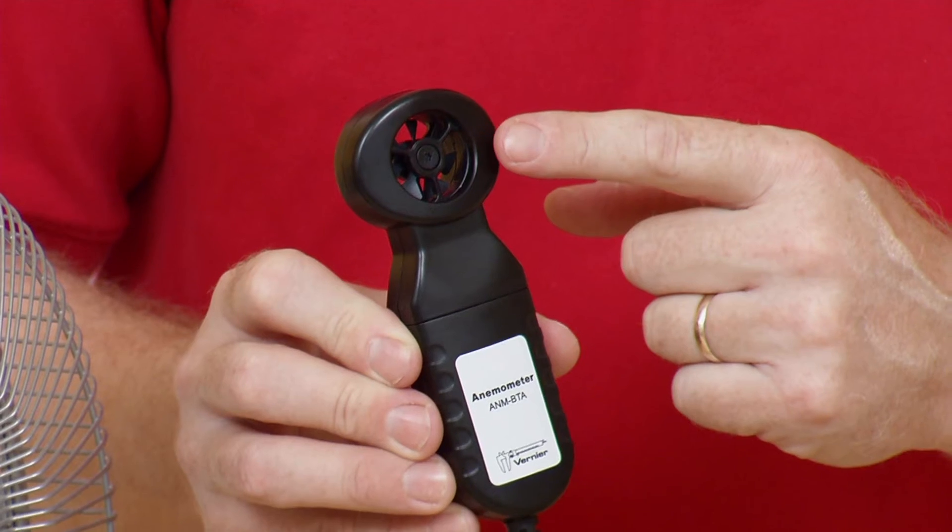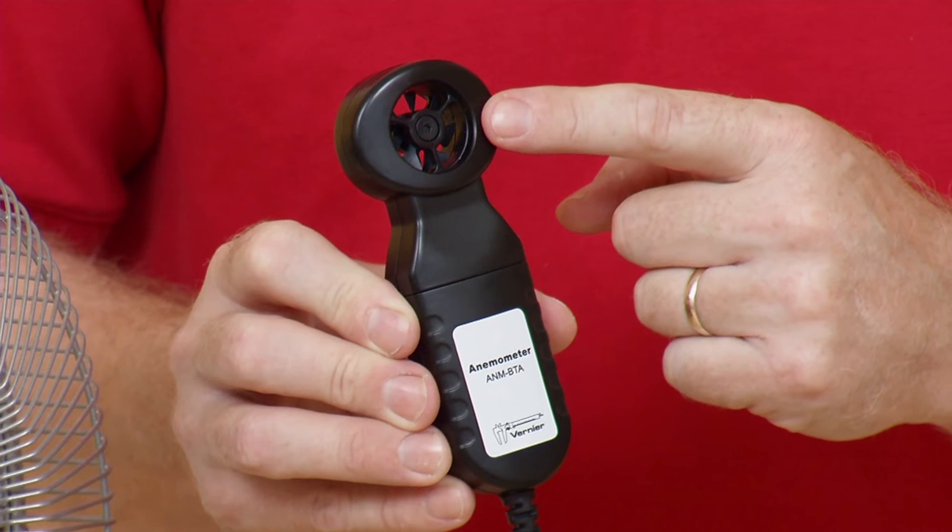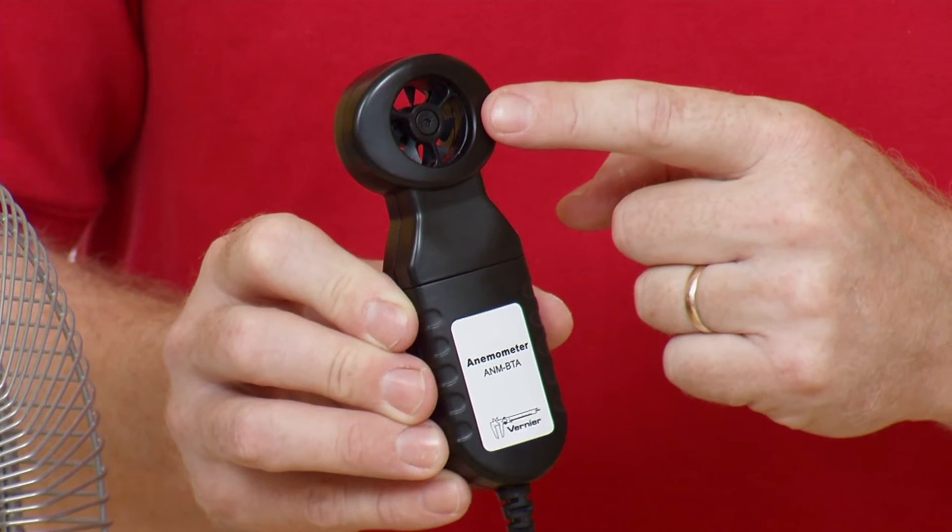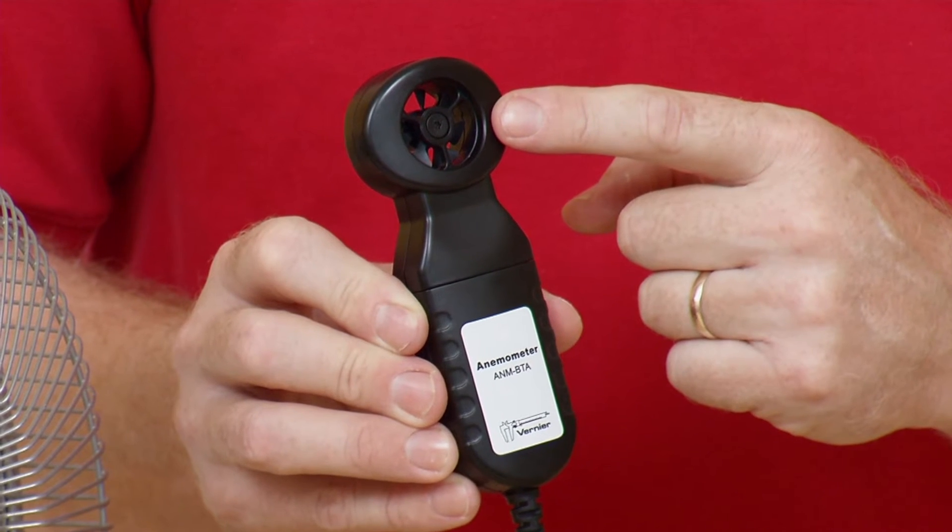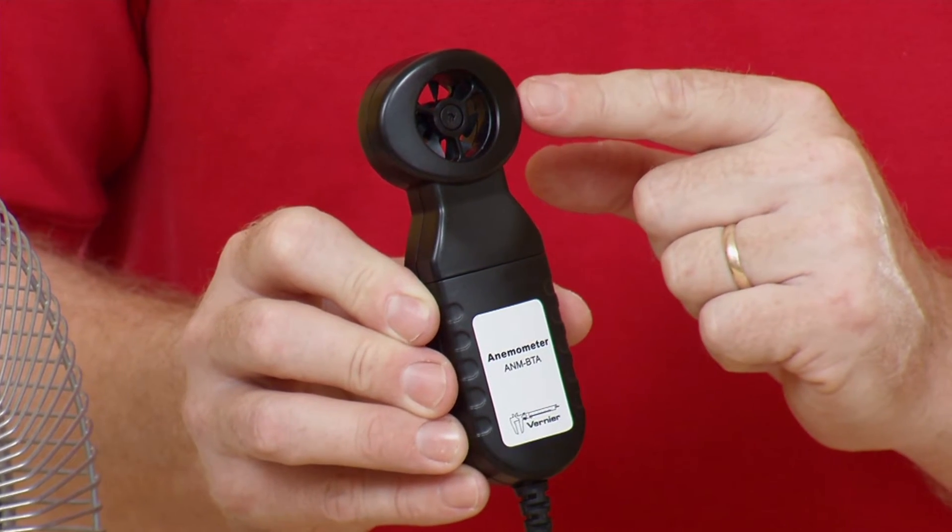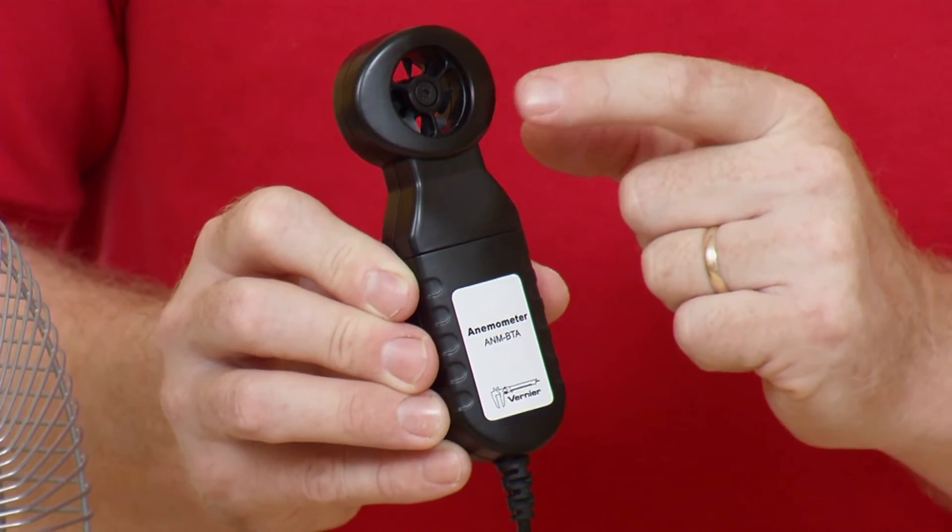And the way it works is that you have the impeller here, and as it turns, it actually turns a magnet, and it induces a current in a coil, and so it produces a voltage that the device can read. So the faster it spins, the higher the voltage, and you get your wind speed reading.